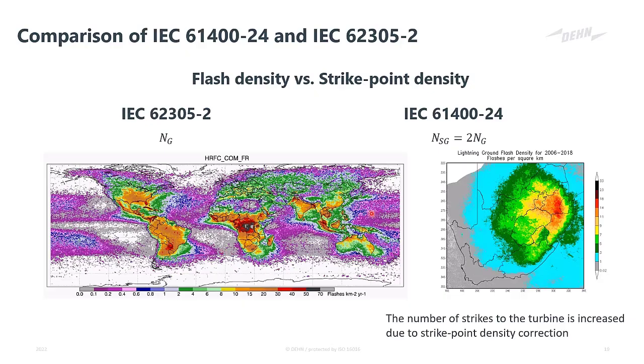As I briefly mentioned, lightning activity is measured as ground flash density, and it's measured in the number of lightning strikes to a square kilometer per annum. Now, this is a map from the NASA Optical Transient Detector. This highlights the lightning flash density globally. So the value for ground flash density is then read off of these type of graphs. The one on the right is a map of South Africa, and the value is then just measured off of this graph. In 61400, the value is converted to what is known as strike point density.